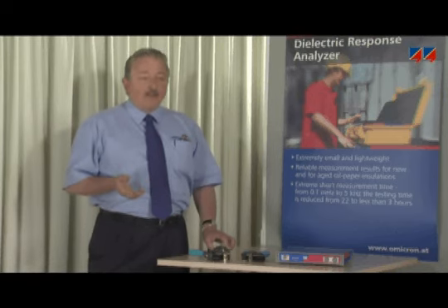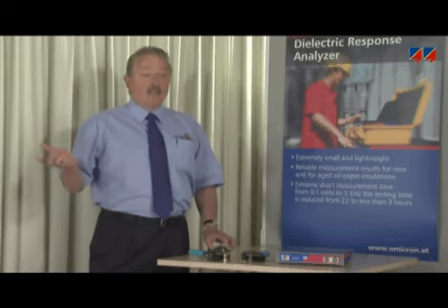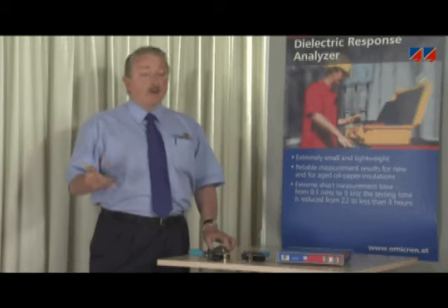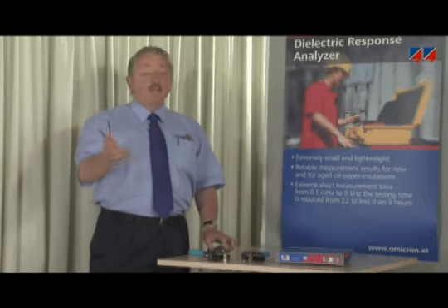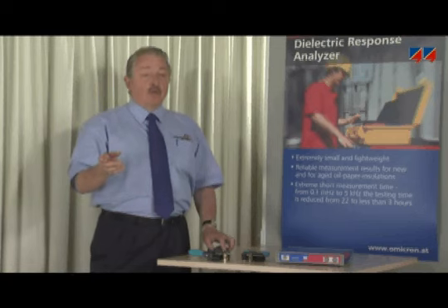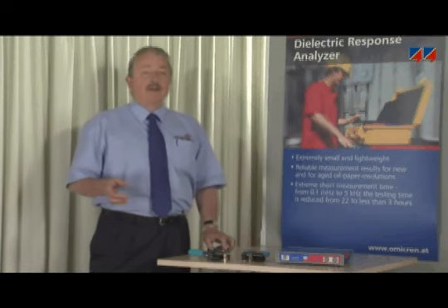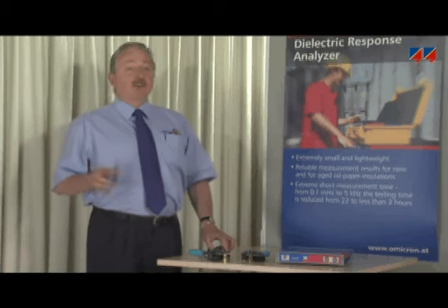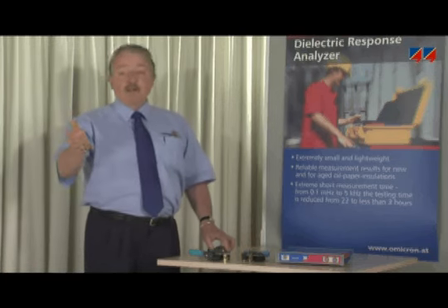For equilibrium, the relative humidity of the air will be identical to the moisture saturation of paper and of oil. For example, a sheet of paper will try to reach equilibrium with the air surrounding it. So, if there is a 40% relative saturation in the air, what will there be in the paper?